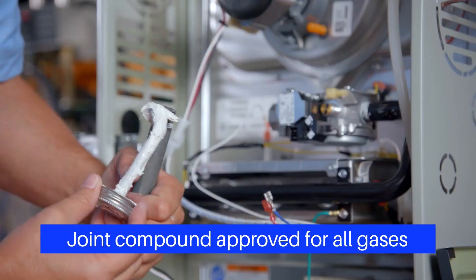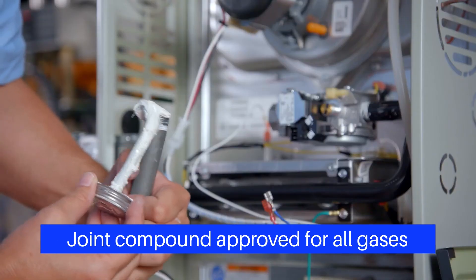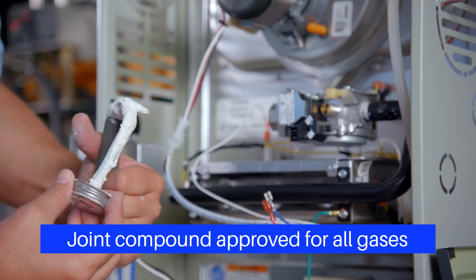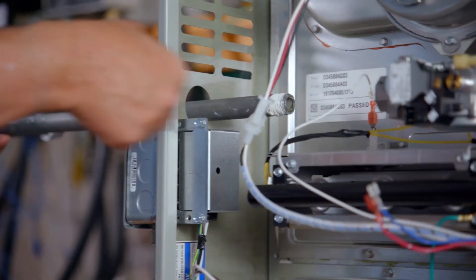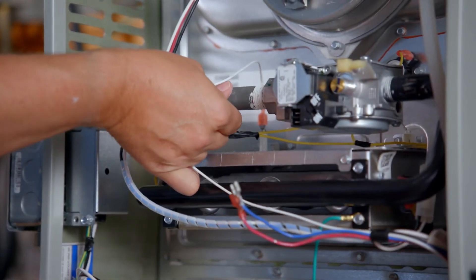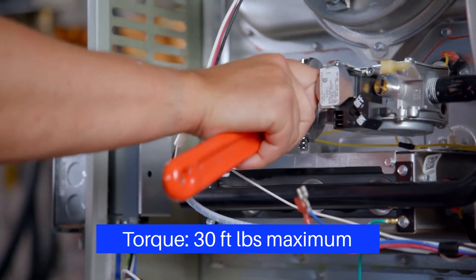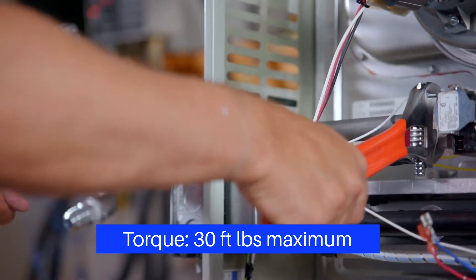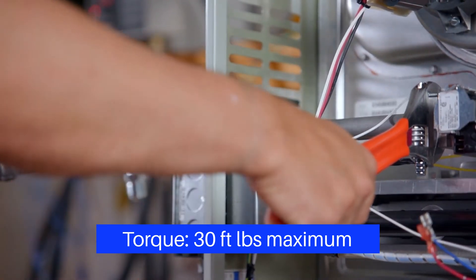Apply pipe joint compound that is approved for all gases only to the male threads of the pipe joints. Do not apply the compound to the first two threads. Hand start the inlet piping, taking care not to cross-thread. Use a vise or open-end wrench to hold the valve while installing piping. Do not tighten excessively, as this may damage the valve.